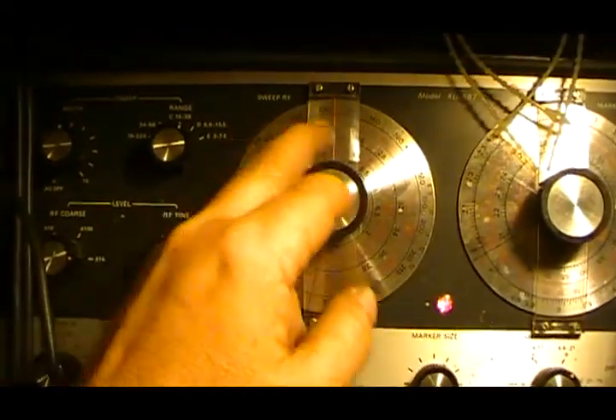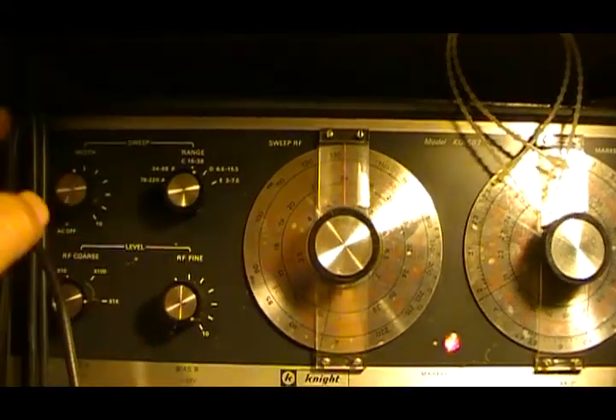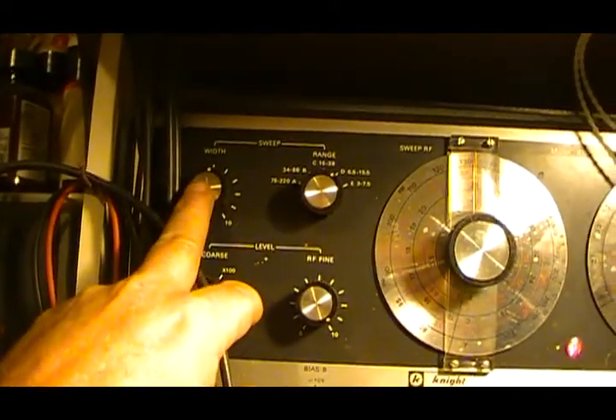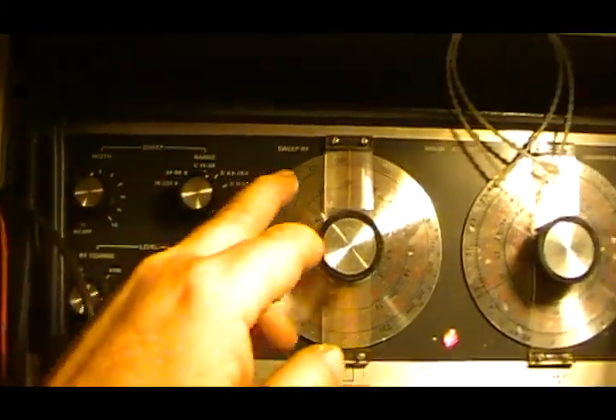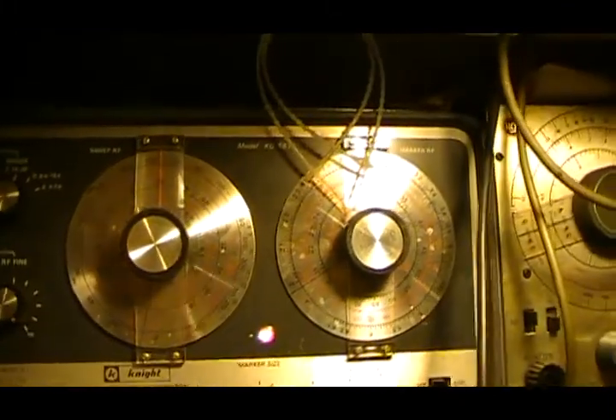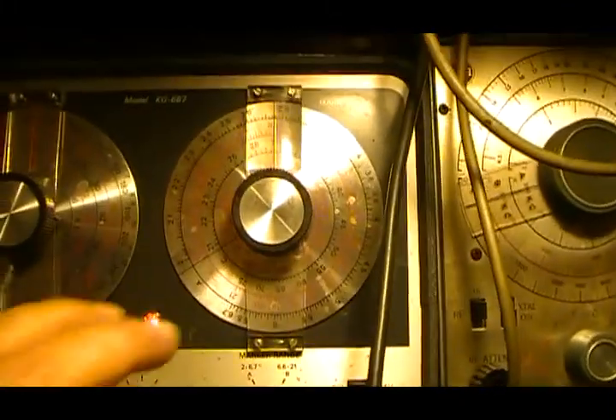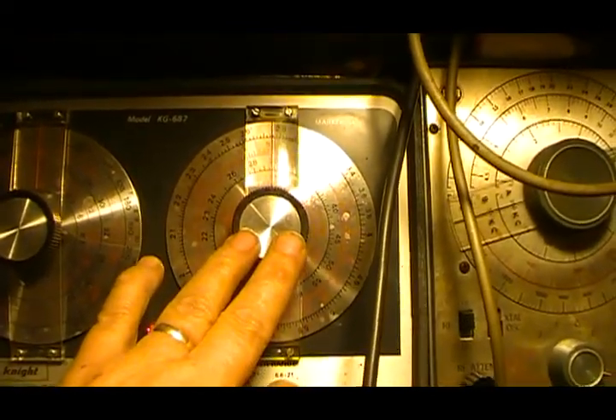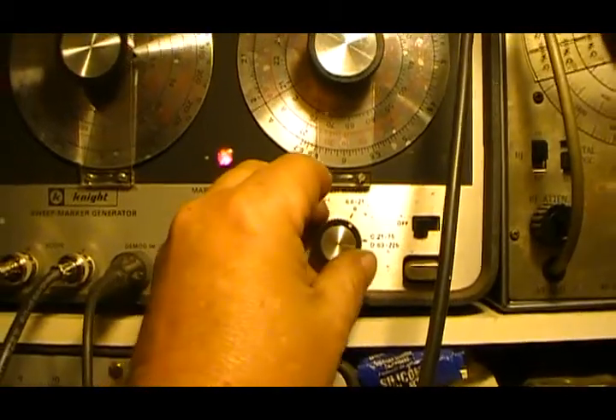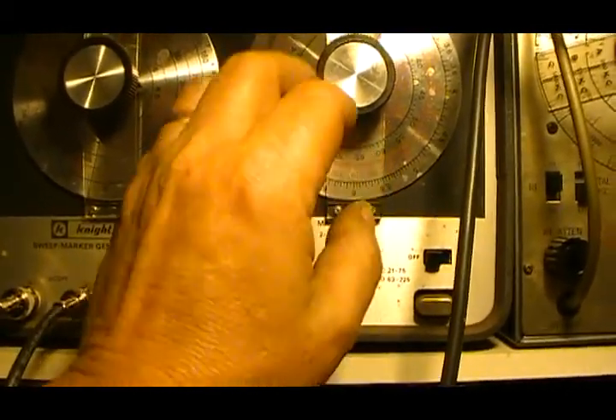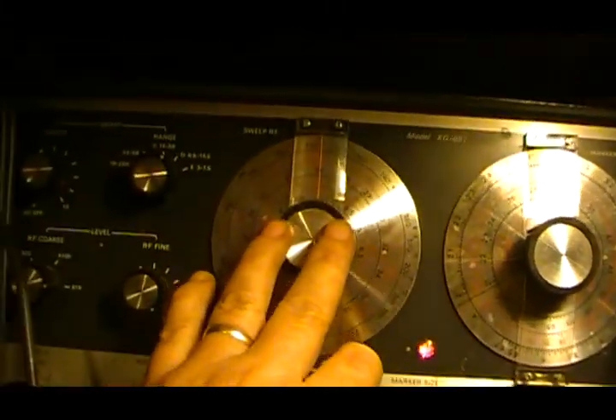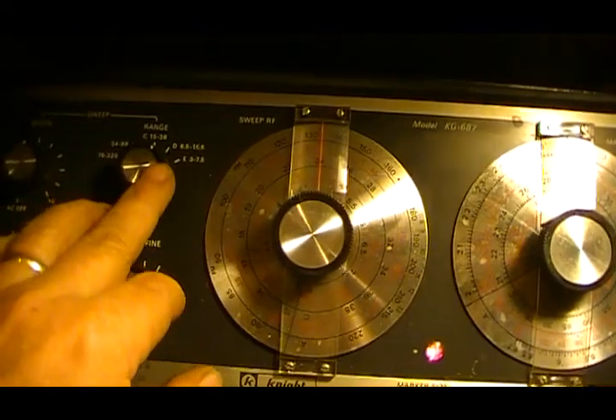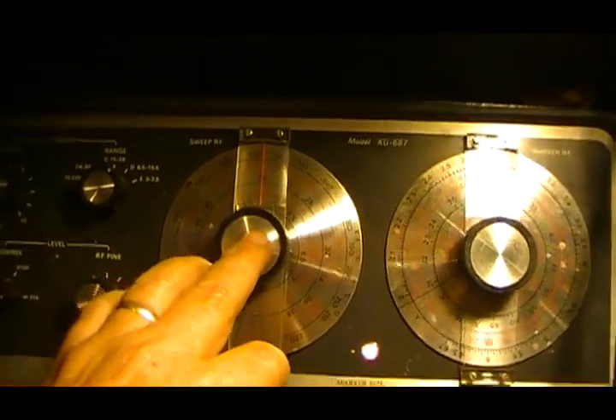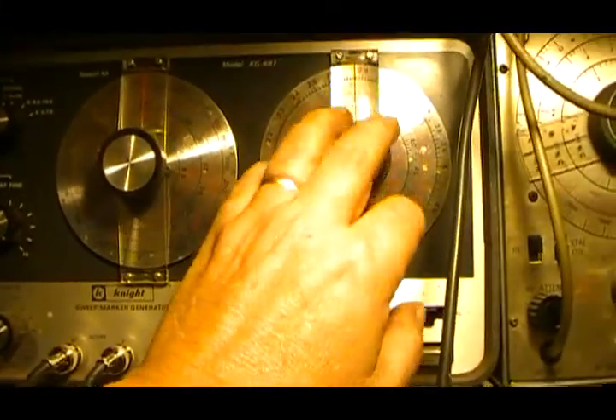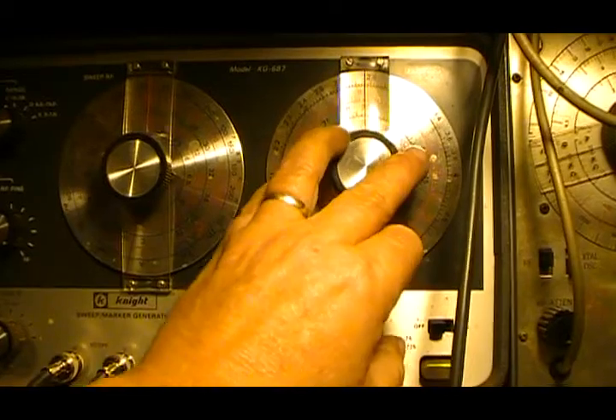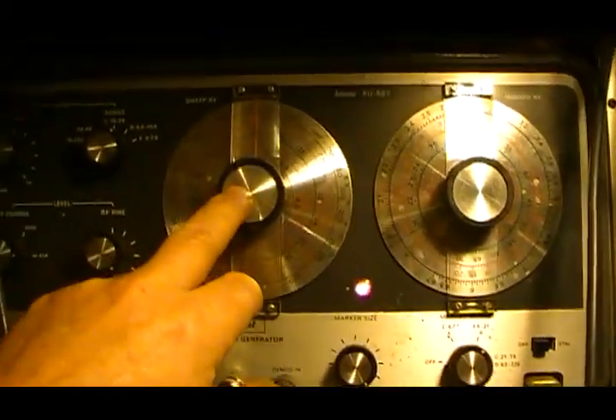So if you pick, like right now I got it centered on 24 megahertz. I believe about right here is about 5 megahertz sweep width, so about 2.5 megahertz either side, or pretty close to that. This dial here is your marker dial, and this switches it to where you want to be on your markers in accordance to where you want to be at here. I guess I'm on the other band here. It's not actually on 24. It looks like about 10.5 megahertz, but this adjusts your marker.